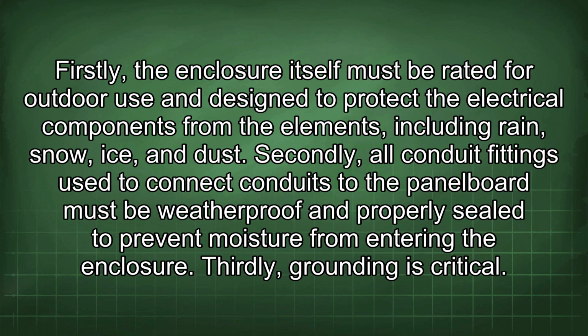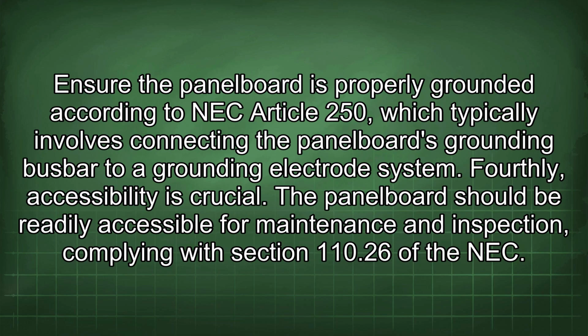Secondly, all conduit fittings used to connect conduits to the panelboard must be weatherproof and properly sealed to prevent moisture from entering the enclosure. Thirdly, grounding is critical. Ensure the panelboard is properly grounded according to NEC Article 250, which typically involves connecting the panelboard's grounding busbar to a grounding electrode system. Fourthly, accessibility is crucial. The panelboard should be readily accessible for maintenance and inspection, complying with Section 110.26 of the NEC.